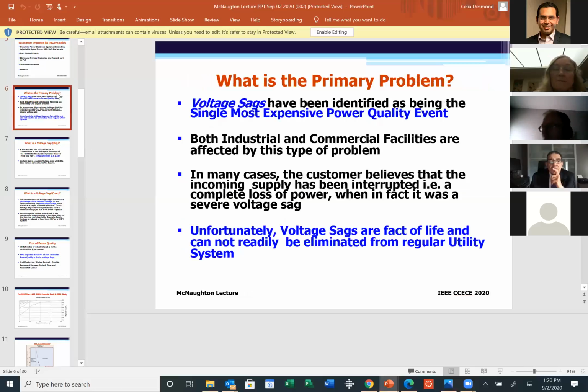Now, what is a voltage sag? Voltage sag has been identified as the single most expensive power quality event. That's why I have focused my presentation on the voltage sag. There are many publications within IEEE and standards that cover the subject, and I will give you a sample at the end so you can read more if you're interested. Typically, a voltage sag could occur in an industrial plant or commercial place on average twice a month, so you could be faced with these voltage sags about 24 times a year.